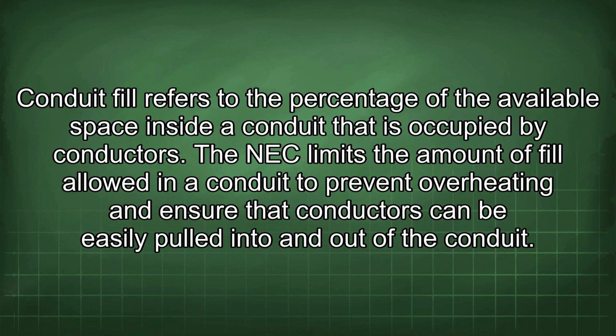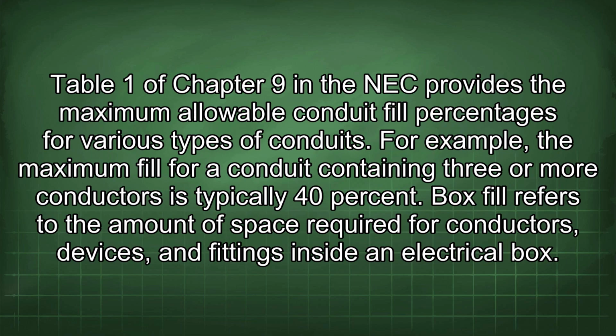Conduit fill refers to the percentage of the available space inside a conduit that is occupied by conductors. The NEC limits the amount of fill allowed in a conduit to prevent overheating and ensure that conductors can be easily pulled into and out of the conduit. Table 1 of Chapter 9 in the NEC provides the maximum allowable conduit fill percentages for various types of conduits. For example, the maximum fill for a conduit containing 3 or more conductors is typically 40%.